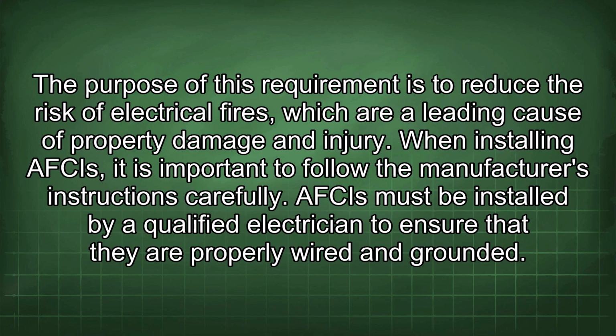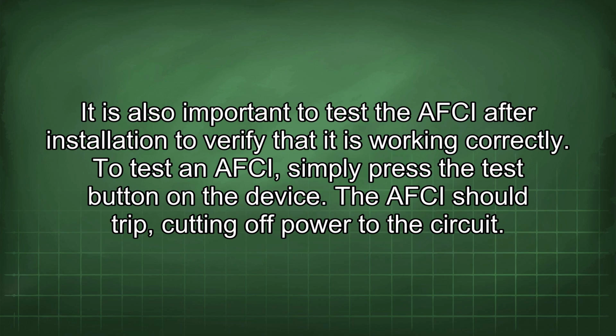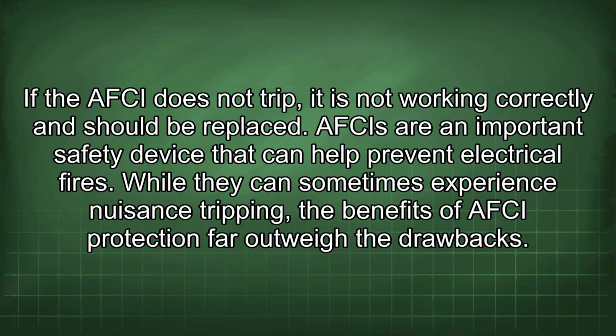AFCIs must be installed by a qualified electrician to ensure that they are properly wired and grounded. It is also important to test the AFCI after installation to verify that it is working correctly. To test an AFCI, simply press the test button on the device. The AFCI should trip, cutting off power to the circuit. If the AFCI does not trip, it is not working correctly and should be replaced.